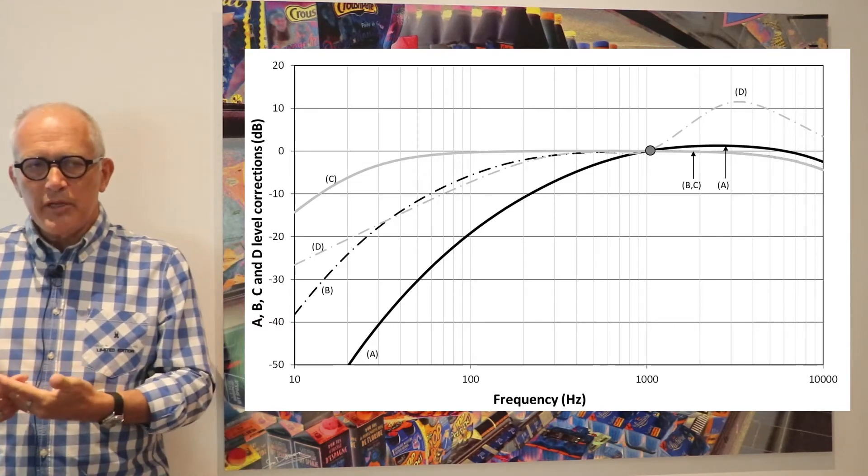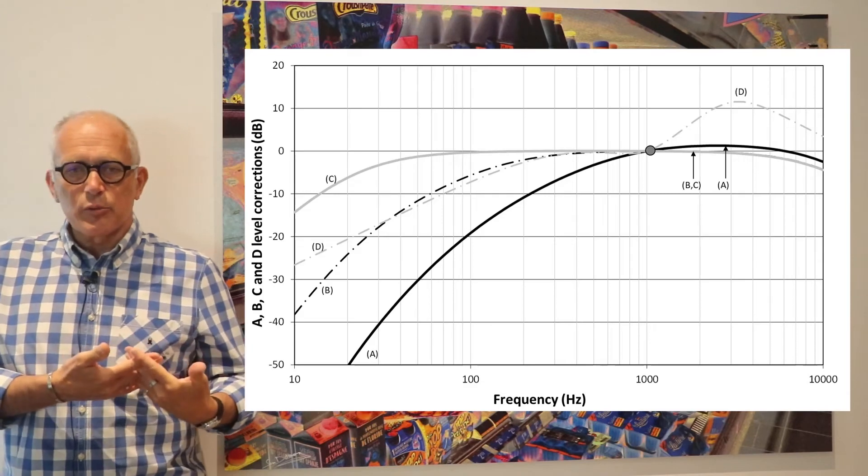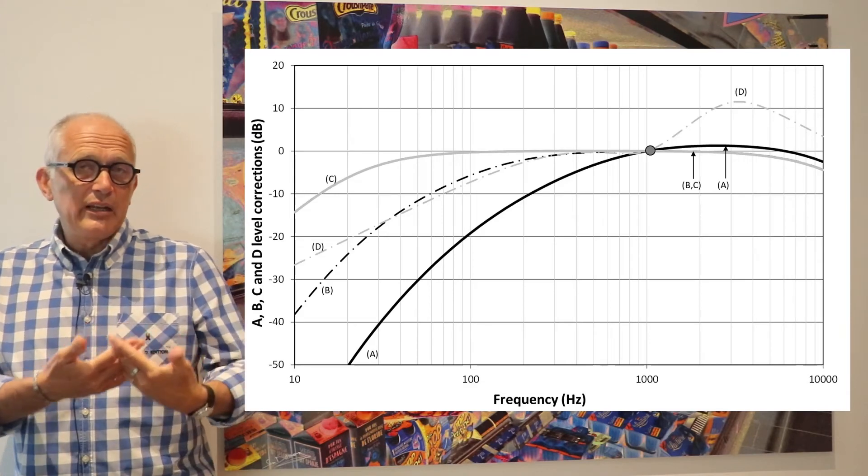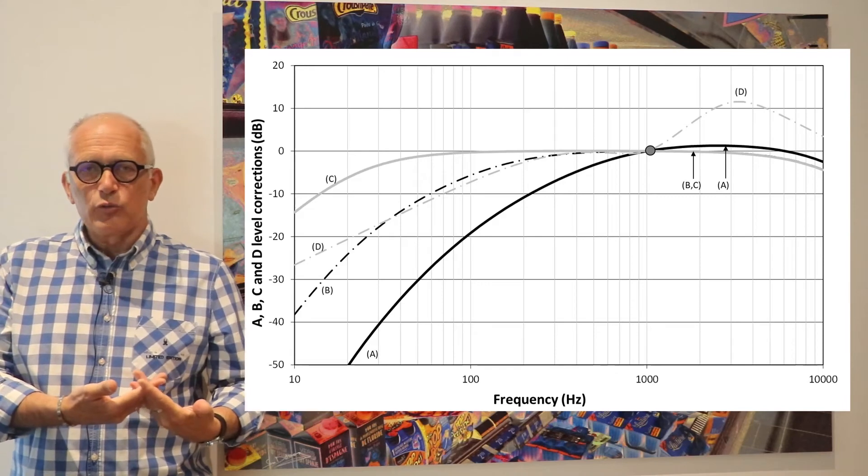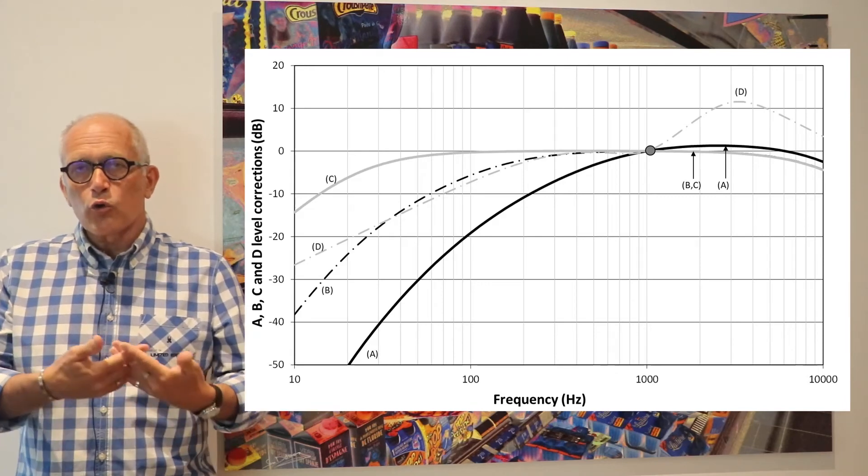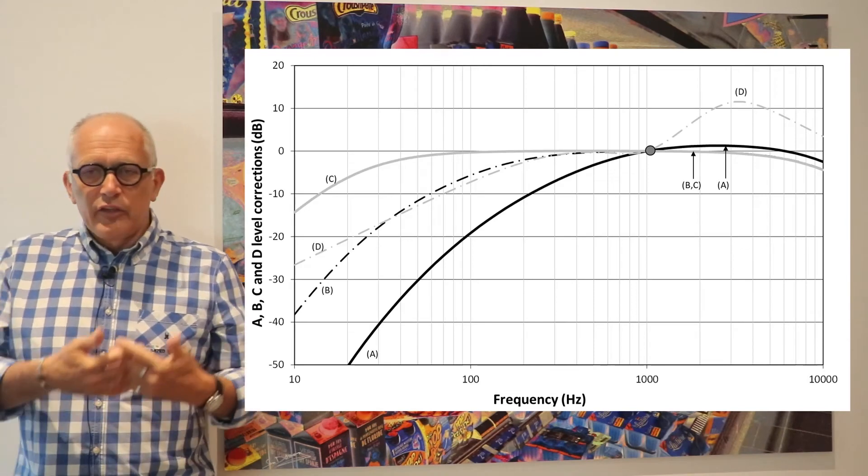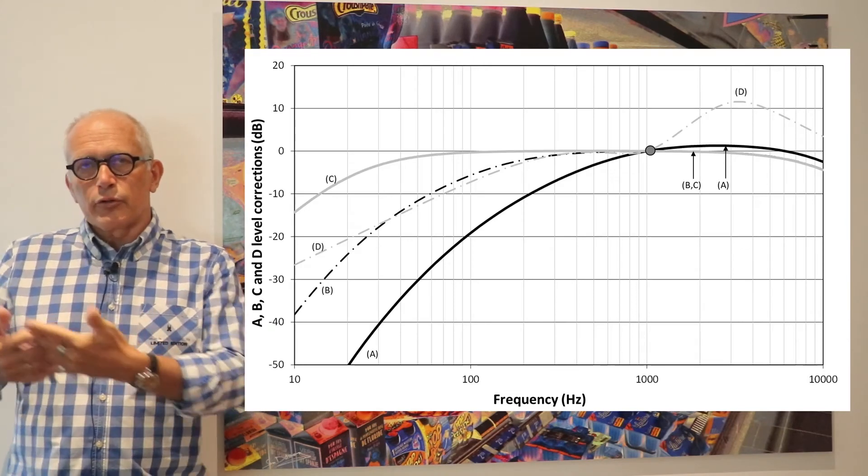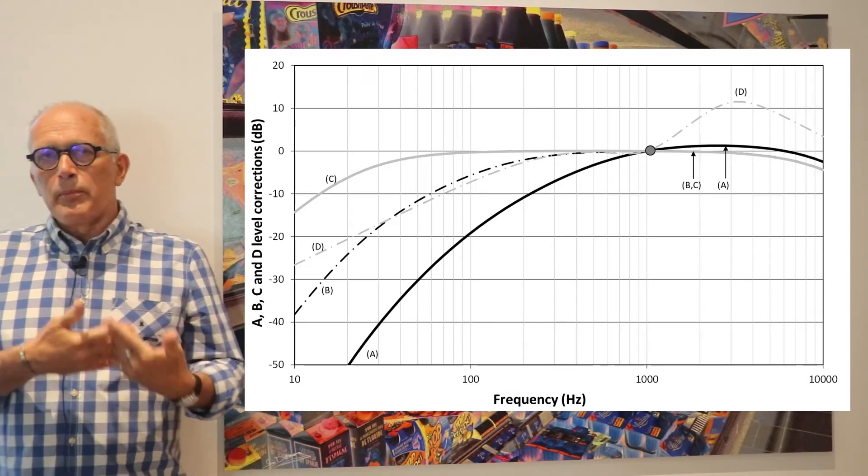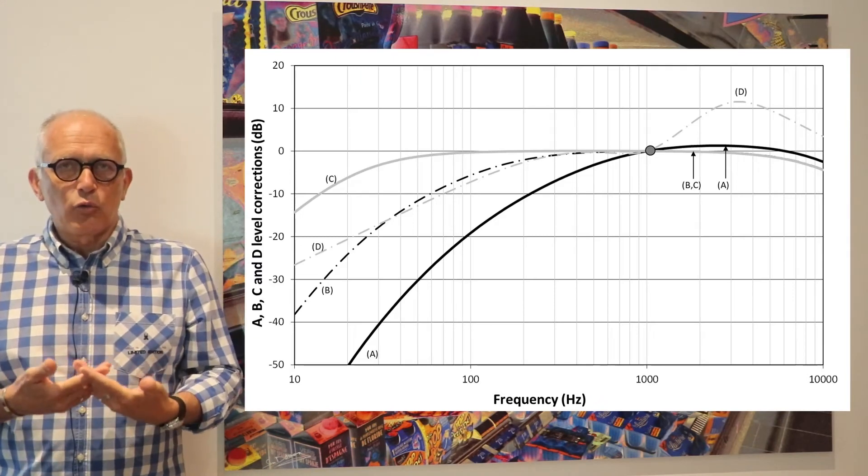And that's why on sound level meters you can take measurements of what is called dB linear without any correction corresponding to the ear sensitivity, or dB A, B or C. The A, B, and C filters are based on the equal loudness contour.